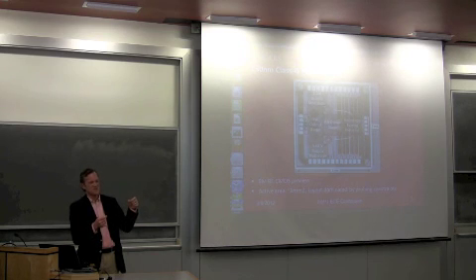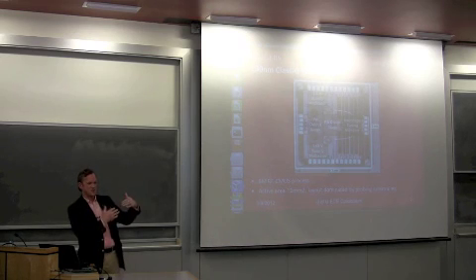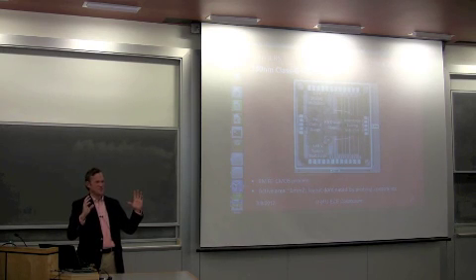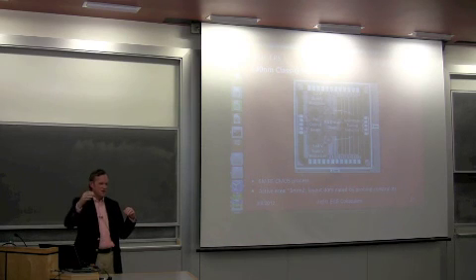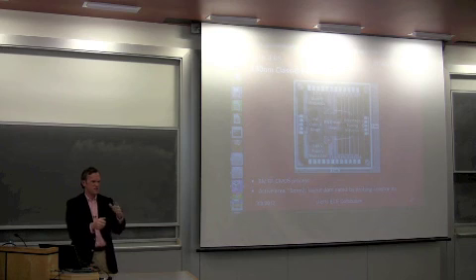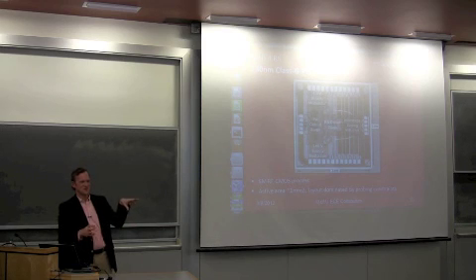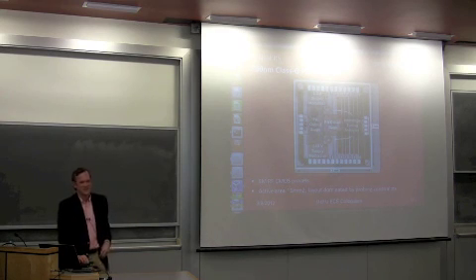Matching the delay in envelope and phase, we need to be within less than 2 nanoseconds at 2 gigahertz. The biggest problem for us is that we don't typically integrate the phase modulator and amplitude modulator together on the same chip, so you have to match these generators. That's actually quite an interesting challenge. Agilent generators all give us a marker on the output. So you output a marker on 2 generators, and with an oscilloscope you can line the markers up, and then the 2 generators are synced in time just by calibrating a delay. In this particular case, we didn't have 2 Agilent generators. We had a Tektronix generator and an Agilent generator, which is why we couldn't do that. Agilent and Tektronix don't like to play together so well. Okay, one last question.